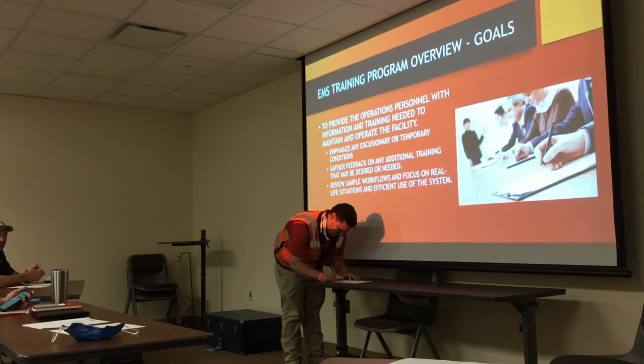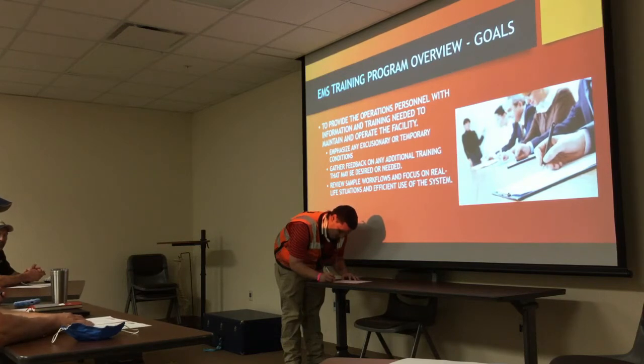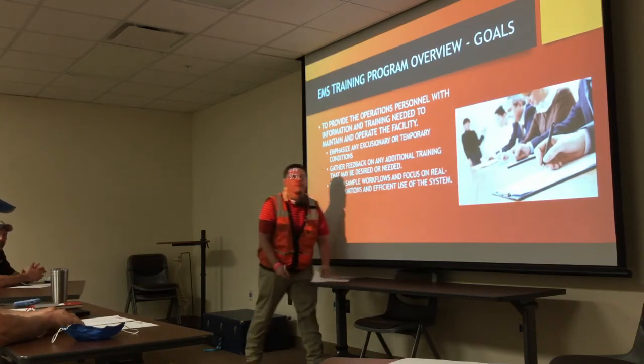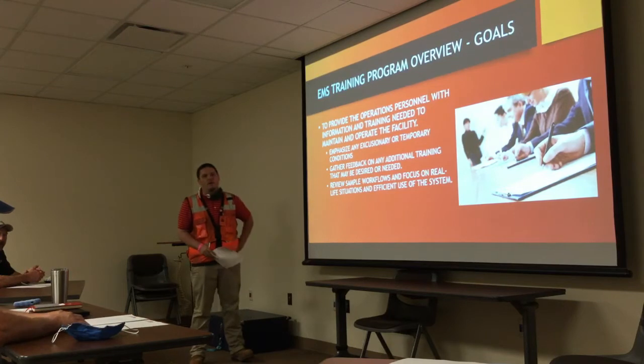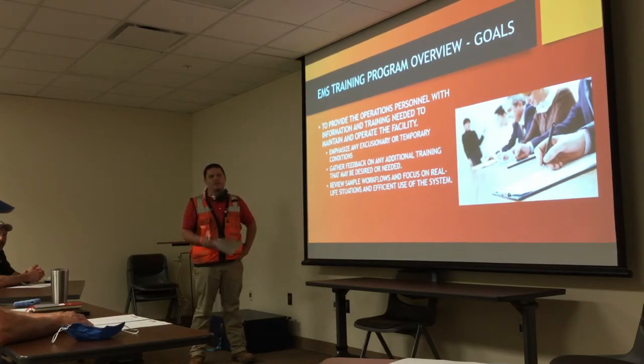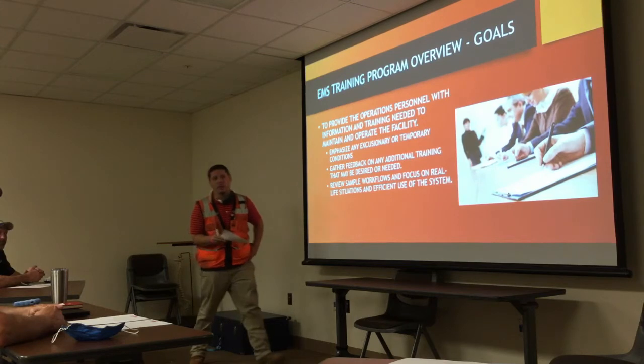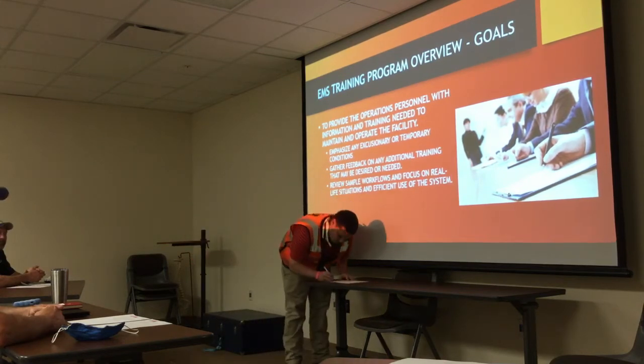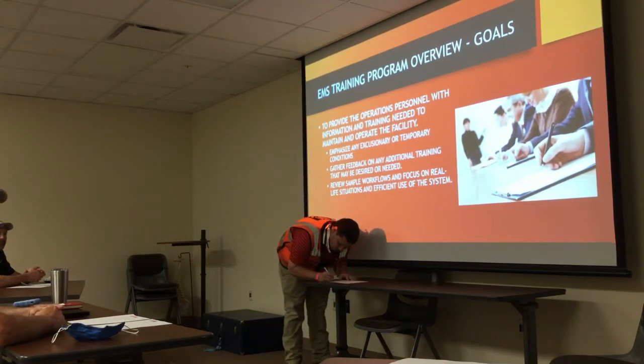There was also something, as we're changing seasons, where the heating water valves at the VAVs would not open unless it was below 65 degrees ambient exterior. That's probably a sequence of operation thing we'll have to look at. We'll check that one, because we don't want that to happen. We don't care, here's the deal, just eyes wide open.